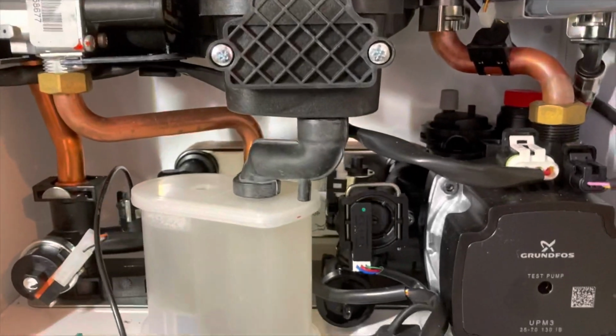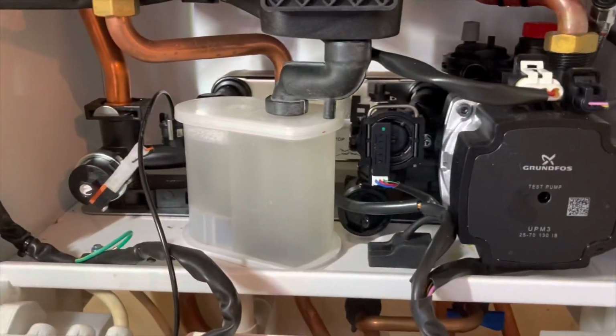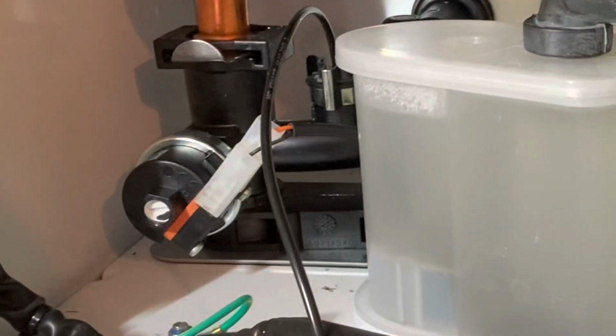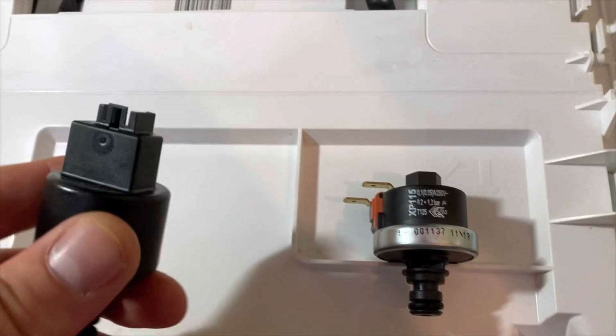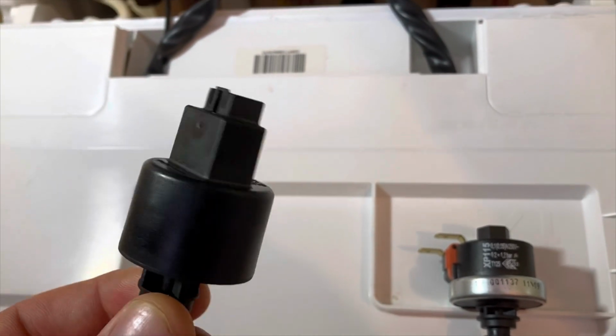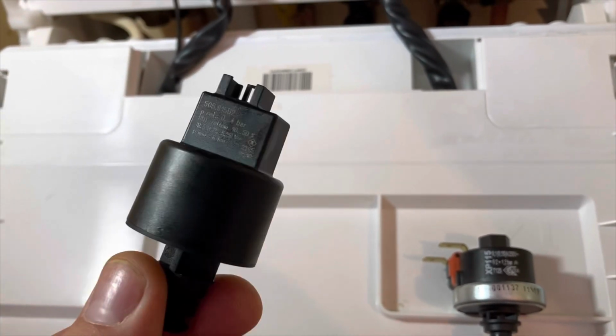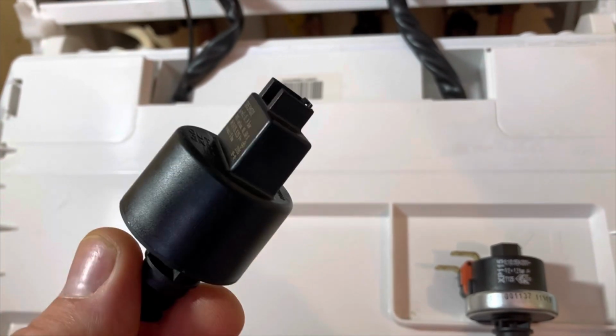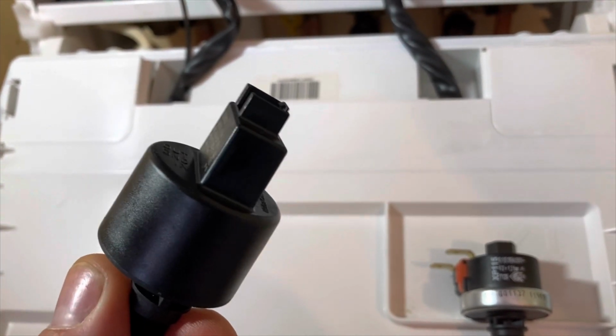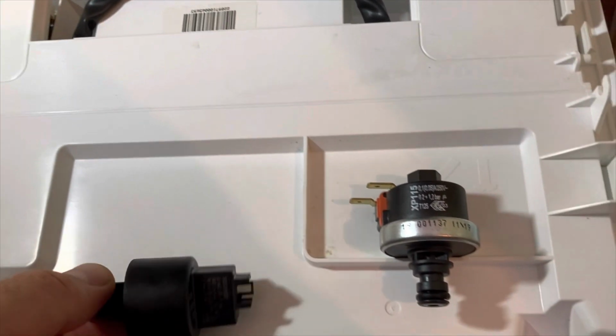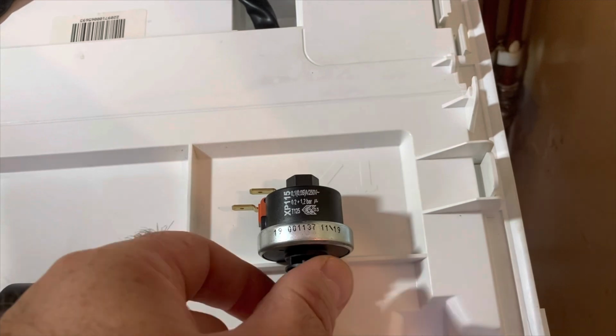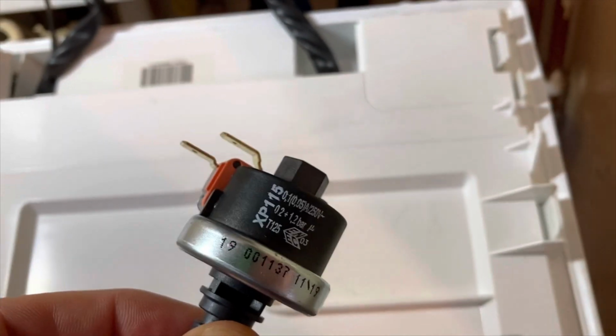What I'm going to talk about is the components within the boiler that measure low water pressure, how they work, how you test them, that kind of thing, and hopefully you'll get some use out of it and some knowledge. So the two main components that we use or have used in our boilers: on our older 2009 to probably 2015 models, we used this, which is a water pressure transducer, and on our current models we use this, which is a low water pressure switch.